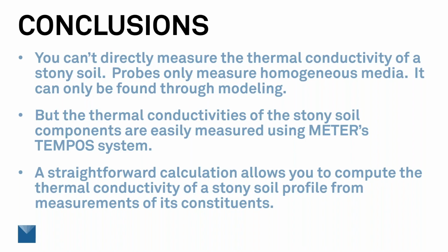There was one question that came up during the presentation asking about converting units to non-metric, and we do have that, at least in the METER TEMPOS system. There is the ability to measure in both metric and non-metric units. So it was BTU per hour, was it per foot? Something along those lines. Sorry about that. Anyway, we do have that ability for those of you, especially working in the United States.